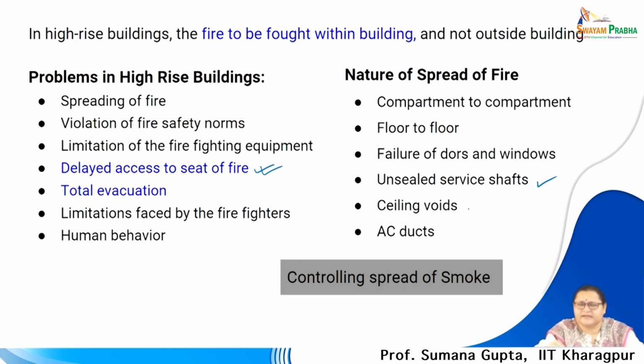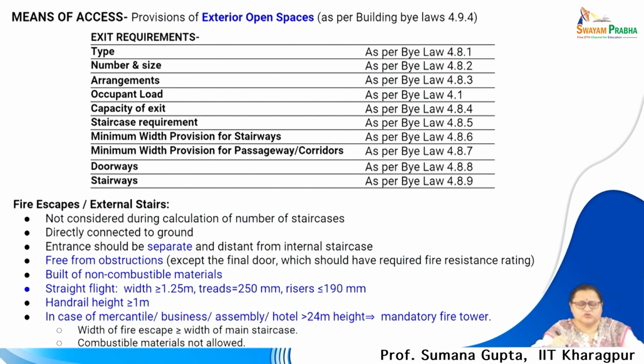Also, we have talked about ceiling voids which go unnoticed, that is, if there is a false ceiling feature in office complexes, it is unnoticed and fire as well as smoke can move through it. AC ducts, as we had talked about earlier, dampers should be appropriately applied. So, controlling the spread of smoke is very important. Fire goes behind the smoke; smoke actually moves faster than the fire, and engulfing smoke leads to suffocation and death.